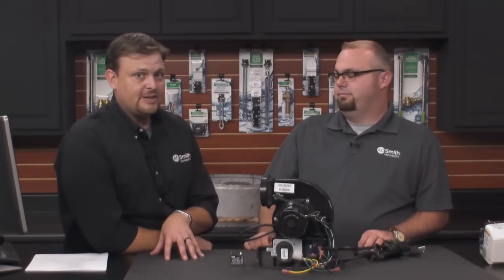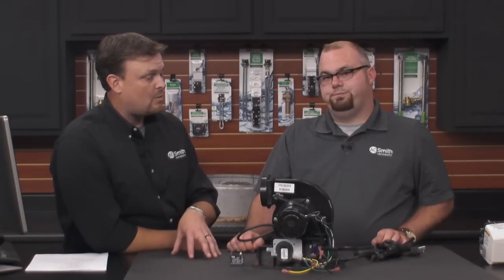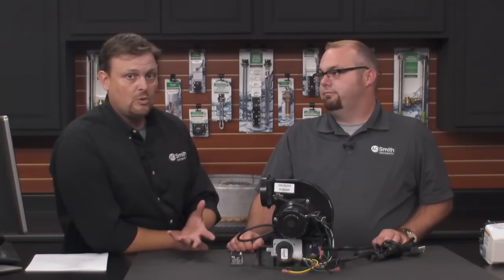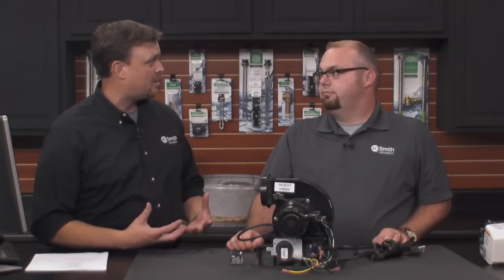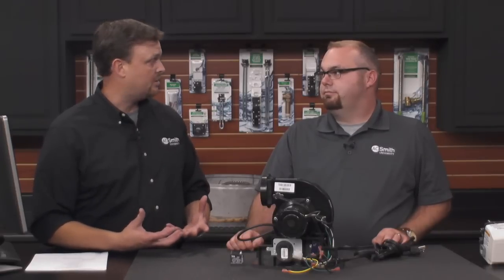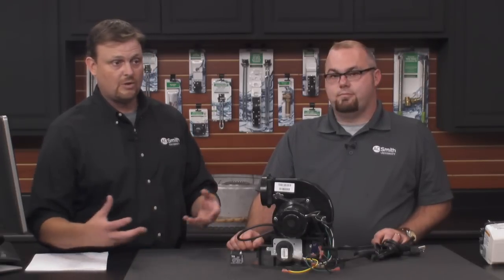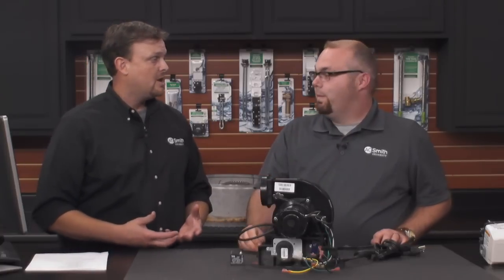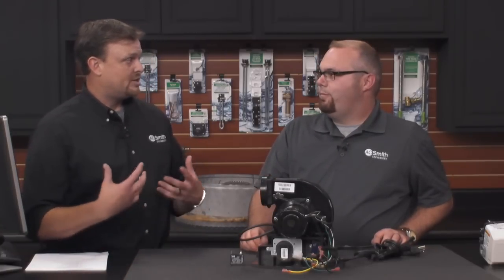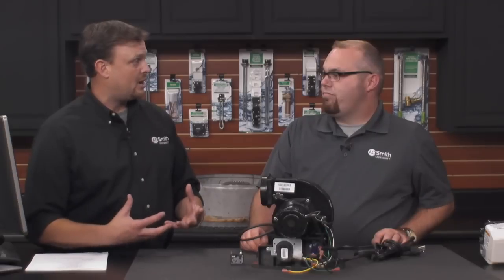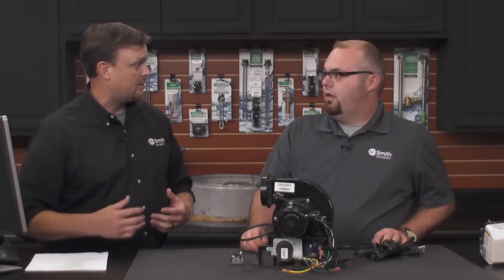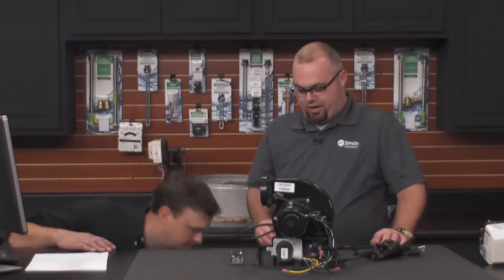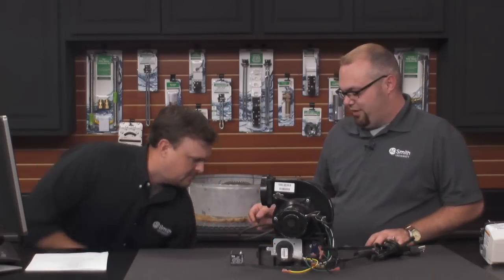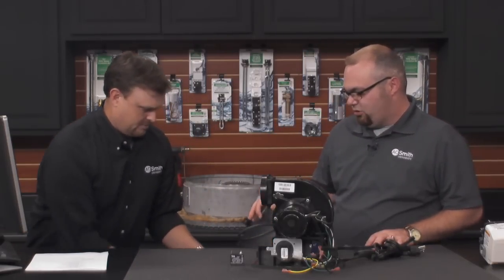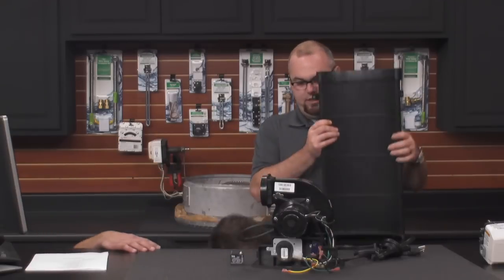Now, another thing that's changed on this water heater is how we're bringing in air. Whereas before with the older style, we were pulling it in on the bottom like a normal water heater, even a standard atmospheric water heater. We pull in air at the bottom. With this water heater, it's kind of changed. We're actually bringing air in a lot higher up on the water heater. Yeah, on this water heater, we're actually using what they call a vade assembly, which is a snorkel or air intake, and here's a piece of it.